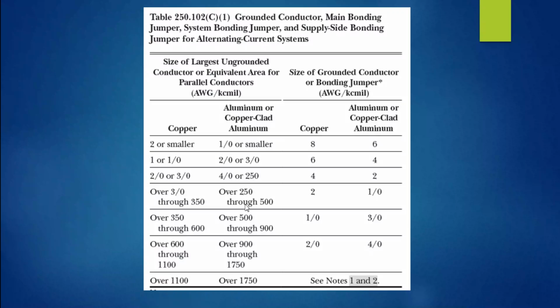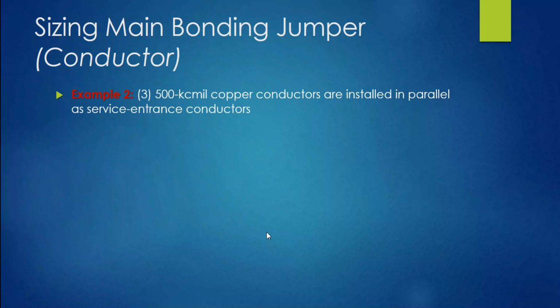Okay. And here's a table we just saw earlier. Again, I could have just done that rather than go to it, but here you go. Here's the difference. We're looking at 4/0 or 250. Our issue was 250 aluminum, and here's how you size it right now. Now you notice these note 1 and 2 here. Anytime I'm dealing with over 1100 copper or over 1750 aluminum, you'll have a note 1 and a note 2 to deal with. So we're going to look at that here in just a second. Now, let's size another one while we're at it.